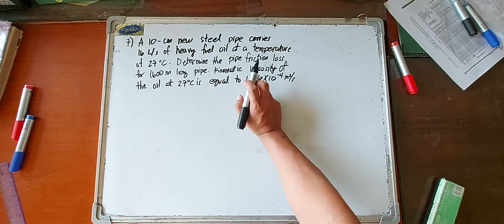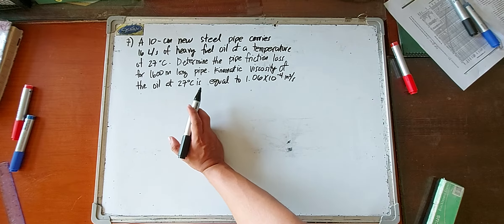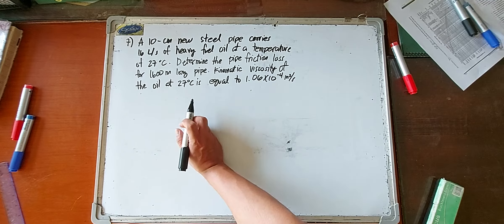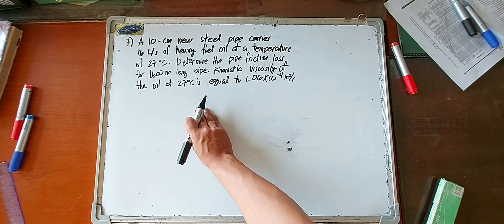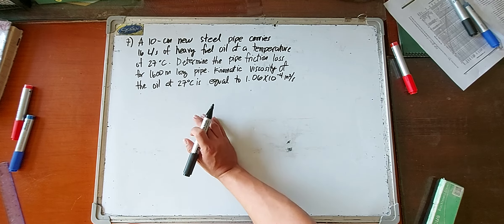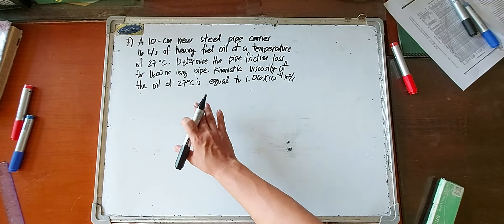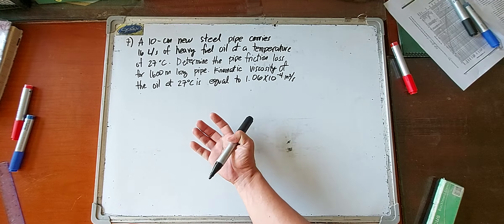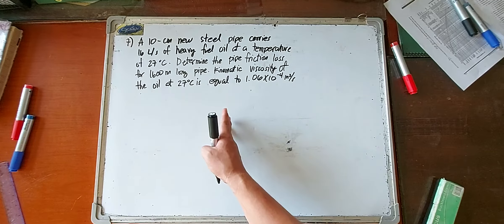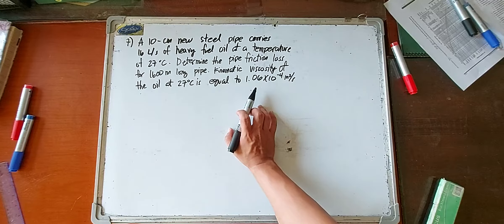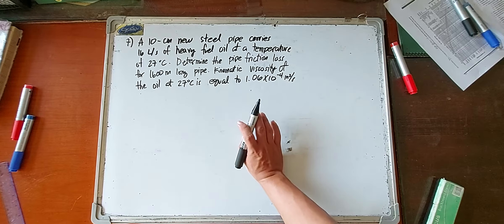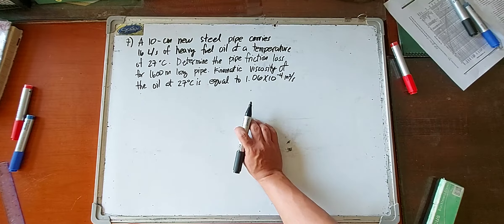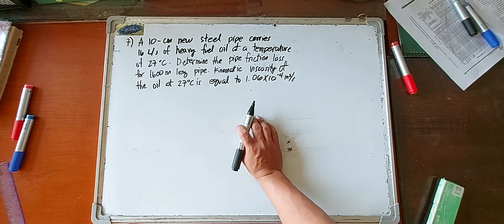So how do we solve for the friction loss of this pipe? The friction factor f or C sub 1 is not given, so we don't immediately know which formula to use. For problems like this, we often use the Darcy-Weisbach formula, because it has a provision to solve for friction loss in terms of the Reynolds number.